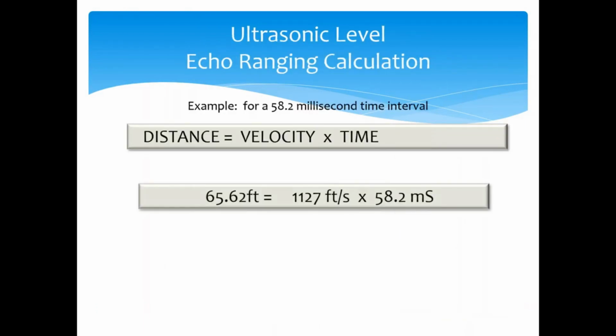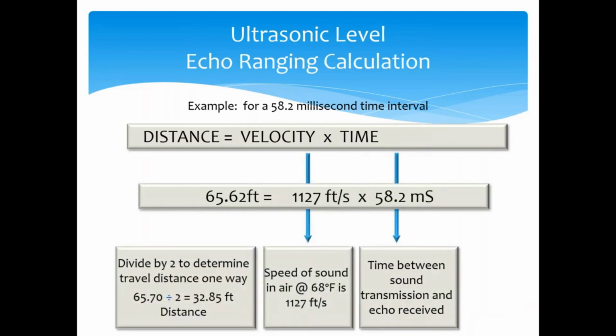So here's just a quick explanation of the math behind that. Your distance is simply velocity times time. Again, we know the speed of sound through air. We know how long it took for that signal to travel from the transducer down to liquid level and back. That gives us our distance. We then divide distance by 2. That tells us our distance away from the transducer. Once again, based on how we have that ultrasonic set up to measure level, we'll subtract distance from overall span, and that will be the level in the tank.